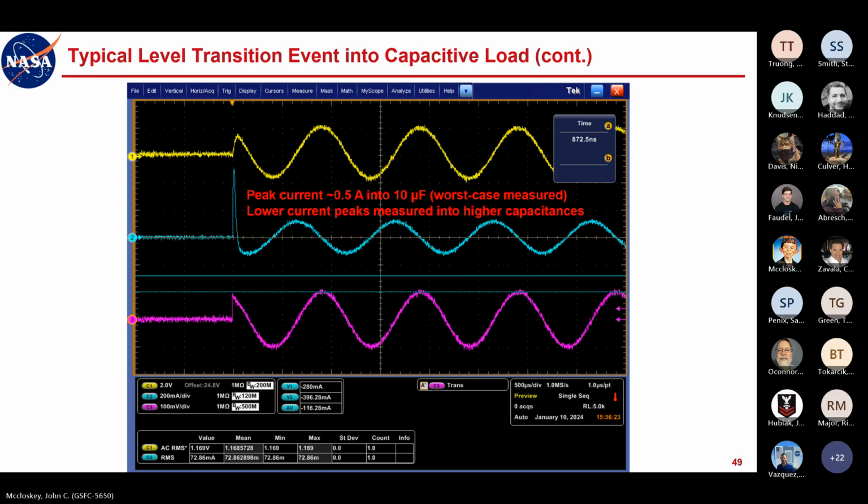So these kind of transients are a little bit more of an extreme test than if it were a completely clean sinusoid. And that was an interesting discussion when we realized what was happening. The box provider initially was saying, well, you're testing us to more extreme conditions than the test method requires. We shouldn't have to be in compliance with these non-standard things that the test is doing. And I can't fault them for making that argument. I didn't buy it, but I couldn't fault them for making that argument.